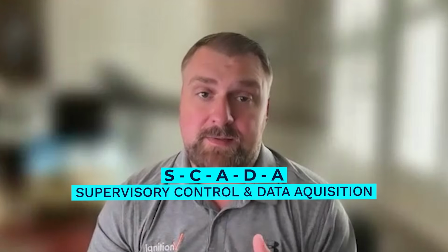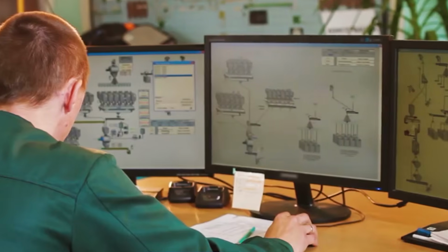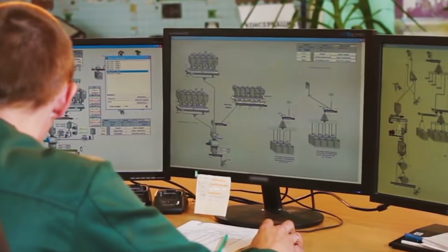You then take that at a higher level. If you've got lots of pieces of equipment out there, you want to be able to centralize all that. You want to see data from your entire shop floor, or factory floor, in one view. And that's what SCADA is. SCADA stands for Supervisory Control and Data Acquisition. It's the idea of bringing all these disparate systems together, being able to see it all in a single pane of glass, and to be able to get insights into data, historize data together, provide alarms for what's happening, and ultimately, get that visualization out to the people that need it. And data acquisition is a huge part of a SCADA system.